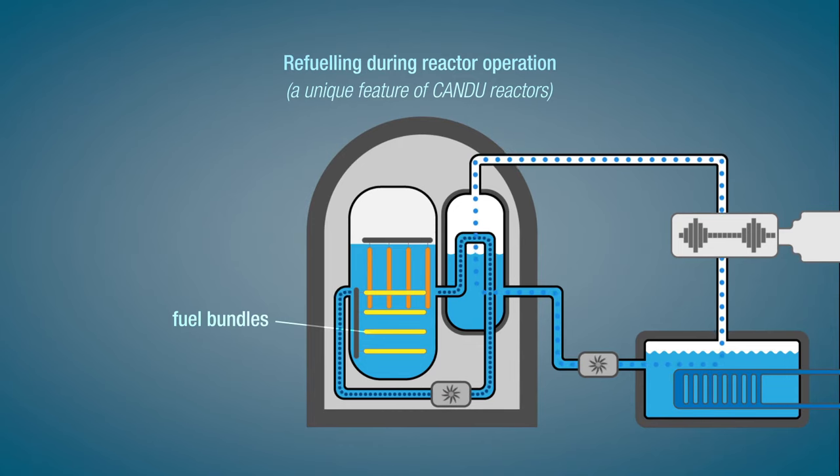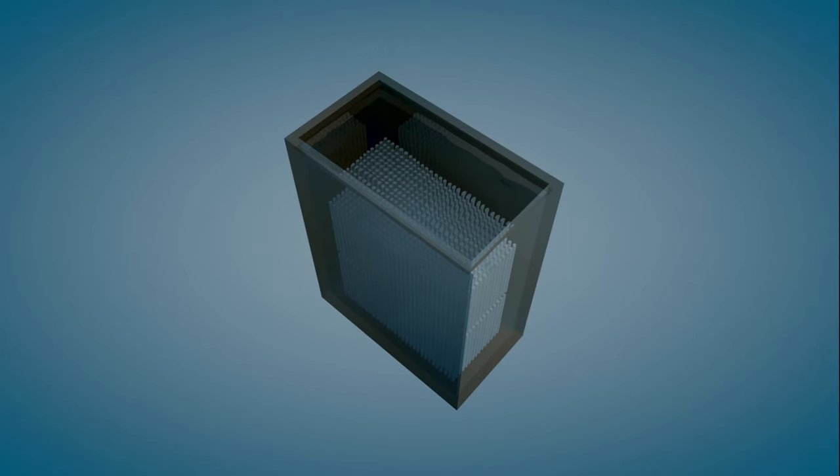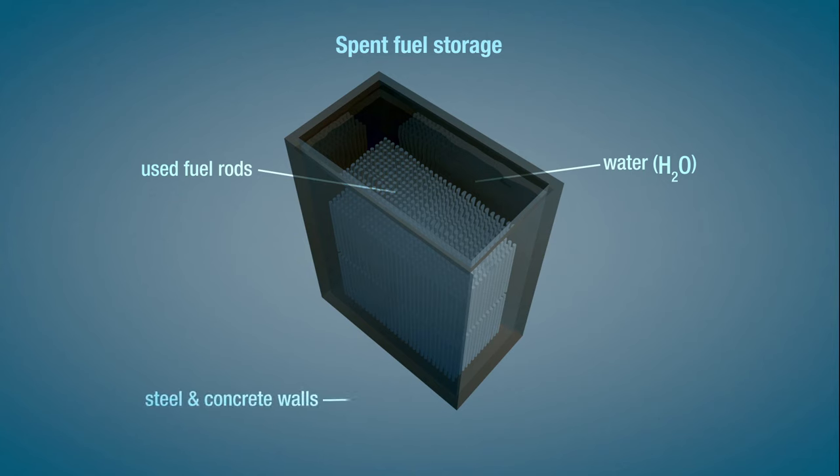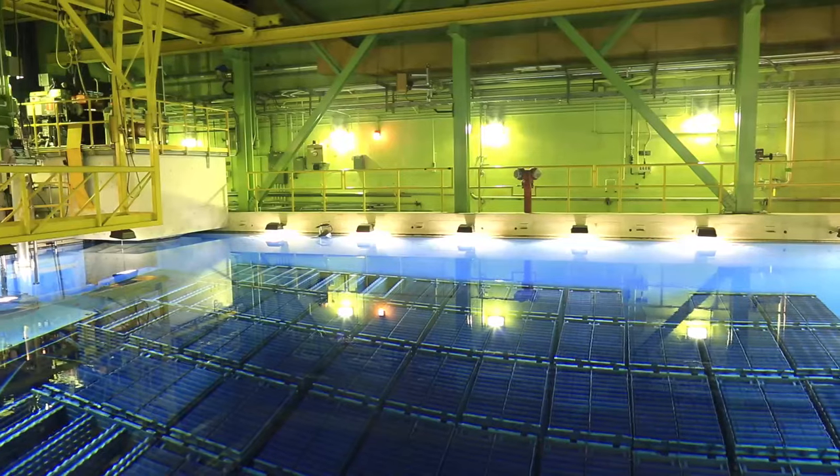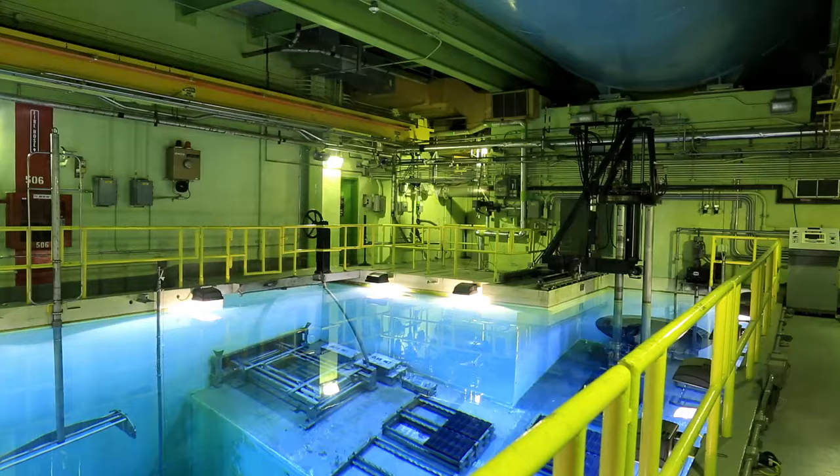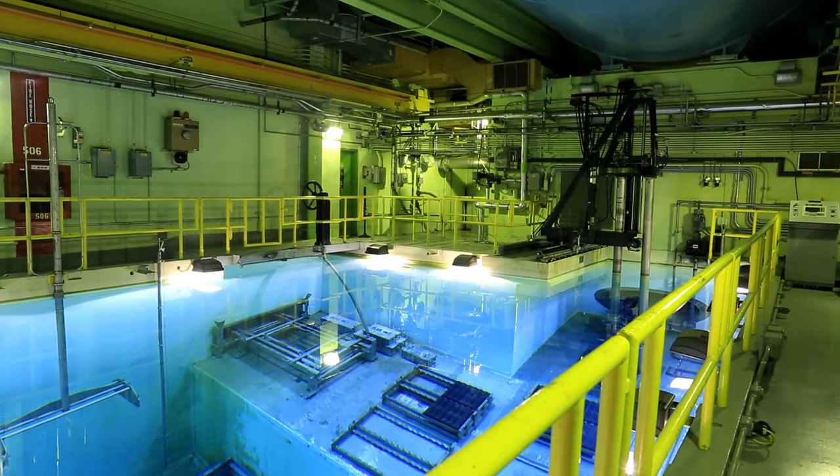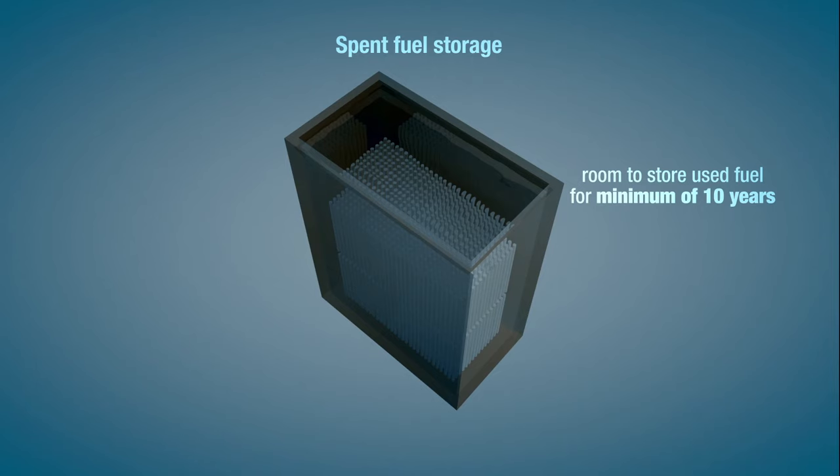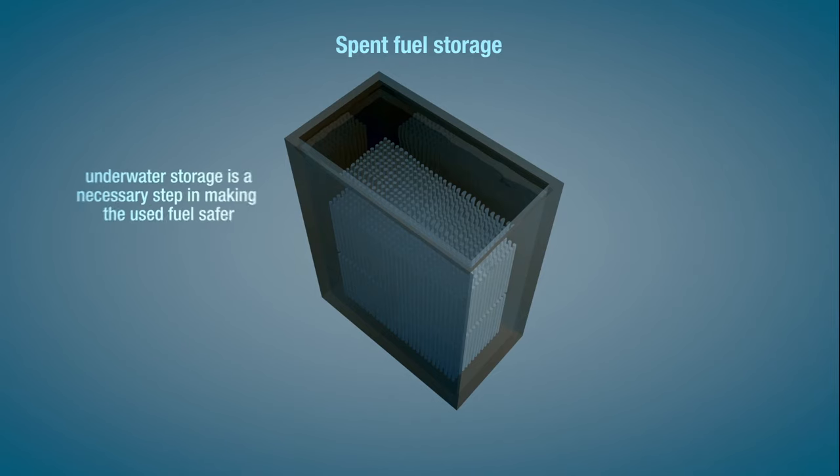Used fuel bundles are lowered into a water-filled discharge bay and transferred to storage bays. All operations in the storage bay are carried out underwater since light water absorbs radiation and heat. These storage bays have room to store a minimum of 10 years worth of used fuel. Storage in this way is a necessary step to make the used fuel safer.